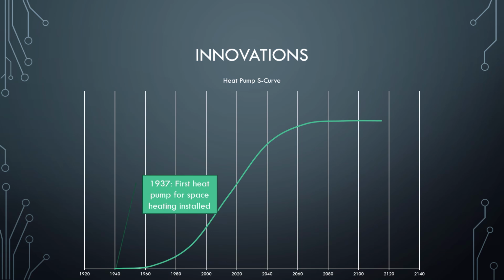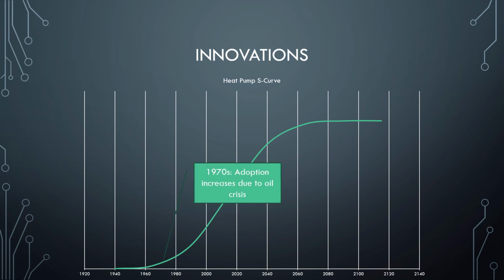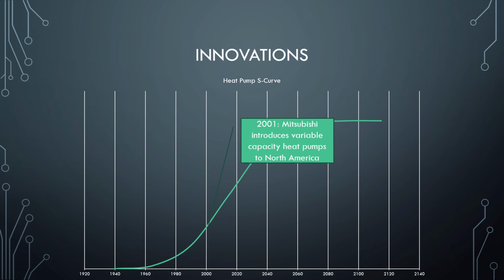The first heat pump for space heating was installed in 1937. The concept has undergone incremental improvement over the last 80 years. The latest key innovation came in 2001 when the first variable capacity heat pump was introduced to North America. This was achieved through inverter-driven compressors that can vary their operating speed to optimize system pressure and refrigerant flow based on current environmental conditions and therefore achieve higher efficiency. Other recent innovations are better refrigerants that can extract more heat at colder temperatures, and electronic thermal expansion valves that, like variable speed compressors, allow the system to optimize pressure and flow based on the environmental conditions.